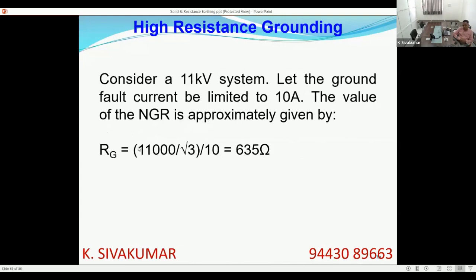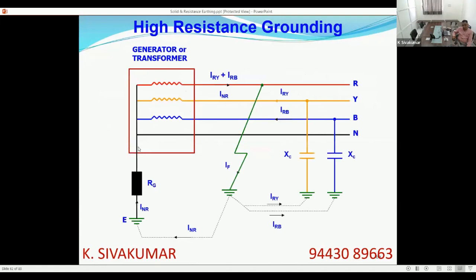So suppose you go for an 11 kV system, the ground fault current should be limited to 10 ampere. The value of the NGR is generally the phase voltage divided by the intended earth fault current: 11,000 by root 3 divided by 10. If you provide a 635 ohm resistor in the neutral to ground path, the fault current will be limited to 10 ampere, like this.